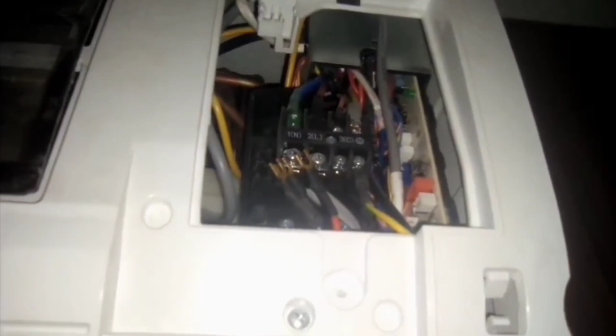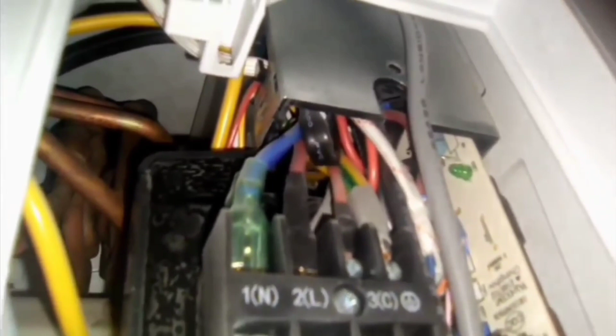We have removed the top cover of the electrical box and we will check the condition of the LED located on our indoor PCB. Here you can see the green LED. We will check its condition. If this LED is off, it means the indoor PCB is faulty. If it is on, it means the indoor PCB is faulty. It should always be in flashing condition.